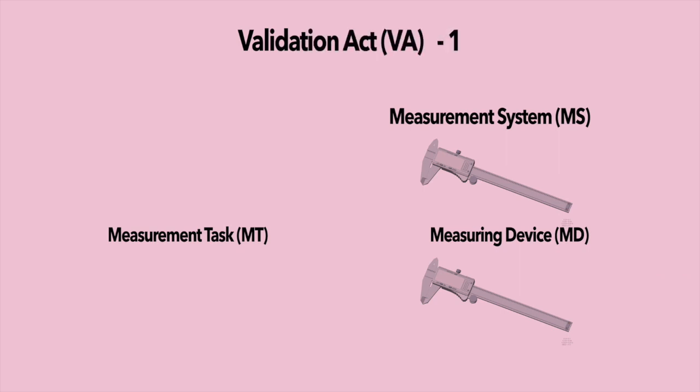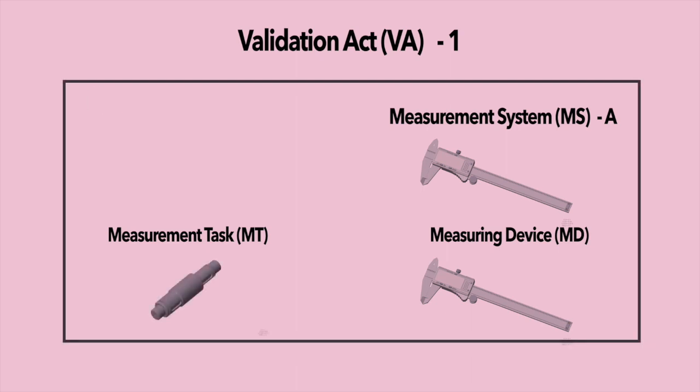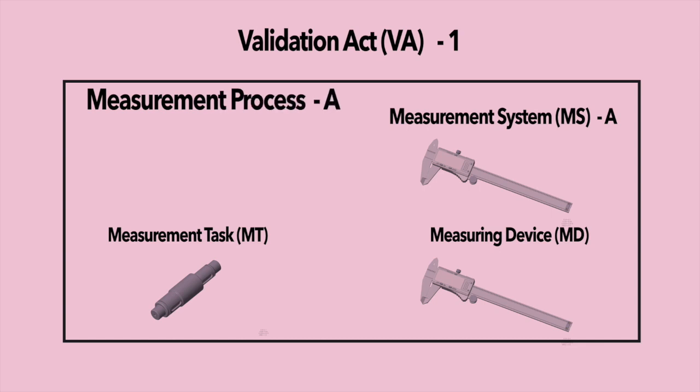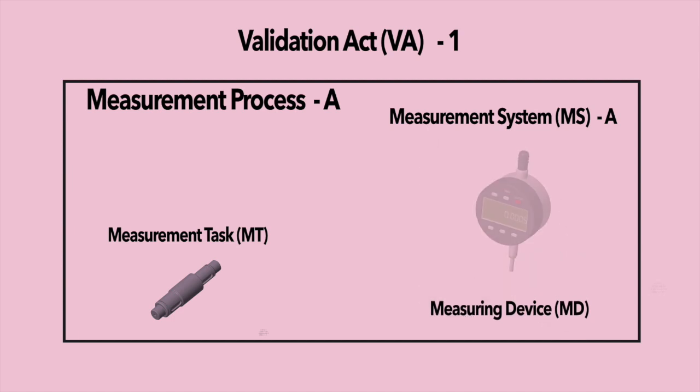And finally, the validation act validates the capability of a particular measurement system for the given measurement task under a specific measurement process. Typically, the shaft is measured on the shop floor with one measurement system and in the lab with another. Although the measurement task is the same, the measurement systems differ, requiring separate validation acts.